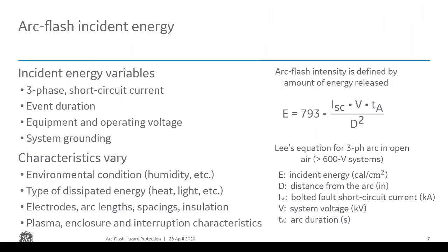The first step to assess the hazard level is to estimate the actual energy created by the arc flash, called the incident energy. Why? Because the amount of energy released defines the intensity of the arc flash. Let's take a look at one of the formulas that we use for determining arc flash energy released. You can see that it's directly proportional to the short circuit current, the voltage level, and the distance between the arc and where you're measuring it from, so it would be from the arc to the personnel. So the farther you are away from the arc flash, the less incident energy we'll see, by the distance squared.